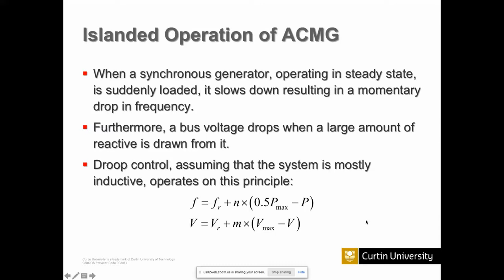Also, the bus voltage drops when a large amount of reactive power is drawn from it. So basically what we will do is use these concepts of what is called droop control. A droop control is where you set a frequency which is proportional to the active power, and you set the voltage magnitude which is proportional to reactive power, that is Q max minus Q.